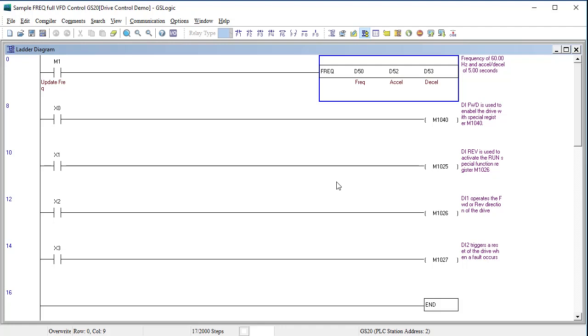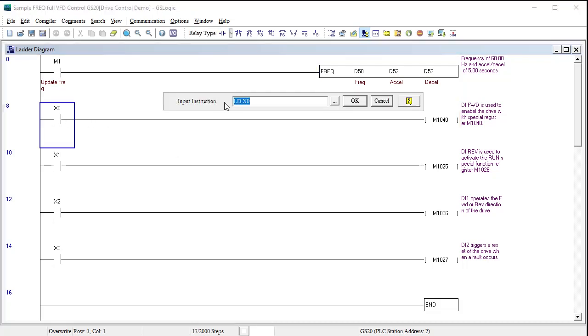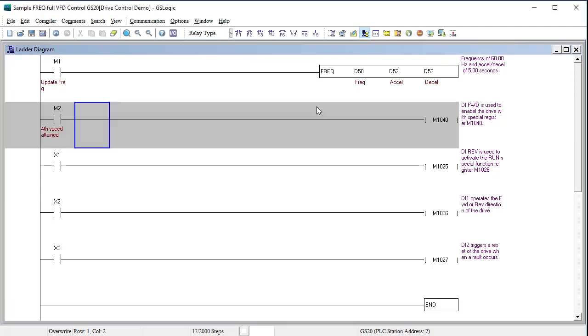That rung used 8 of our 2000 steps so the next rung starts at step 8 where digital input X0 is used to enable the drive using this special function register. Let's change that to M2 so we don't have to wire up a digital input for this demo. Keep in mind, this is not the run stop command, it just enables the drive outputs.